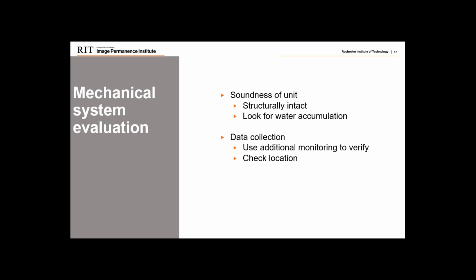Really just addressing each point throughout the system and getting an idea. We want to check the locations, not only of the loggers in the space but of our loggers in the mechanical system, and make sure we have them in the right position. We're getting a good air mix, if you will, but also a good reading. Do we have a proper location in our space to read really what's happening? We're not reading a microclimate that's giving us a false reading.